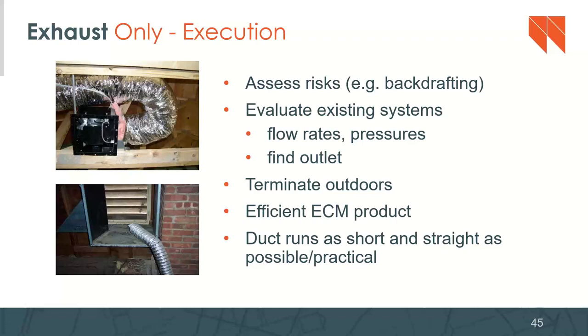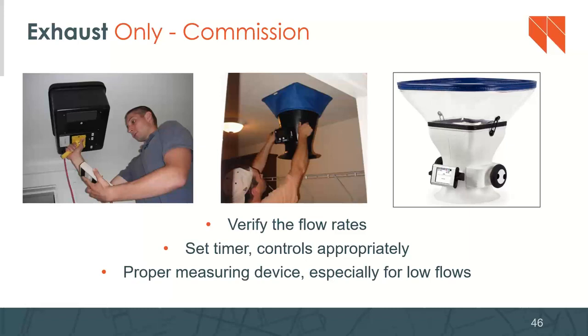So again, you can have a fan that says on the box it's rated to 50 or 80 CFM, but that rating is done at a specific static pressure. That static pressure is based on a length of duct and how many bends are going to be in it. So having it be straight is preferable. Also, with exhaust only, you want to commission it. We find ventilation flow rates are sort of the second biggest reason that we've got issues on the buildings that we test.